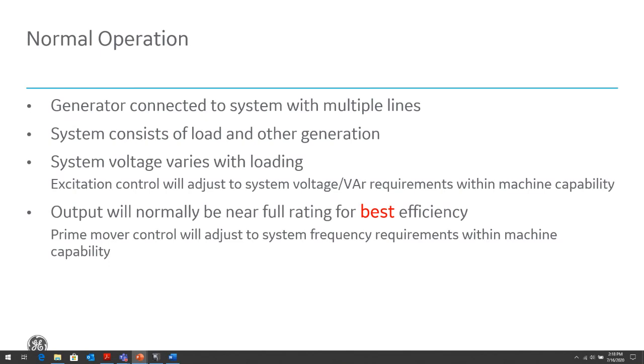When our generator is operating for best efficiency, it should be operating near or close to the full load rating. So usually, if a generator is called upon to operate or be in service, we want to be operating as close to full load for efficiency purposes. There are generators that, when they're called upon to operate, are not necessarily going to be operating under full load because of the requirements of our loading. If our load doesn't require the full load rating, then obviously we need to derate the equipment and run it at the load levels.